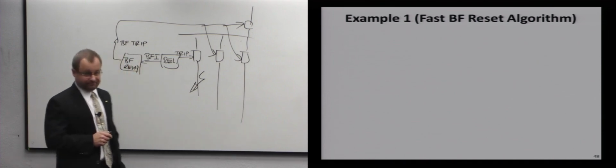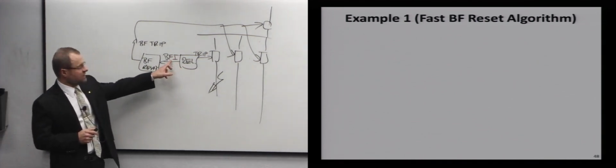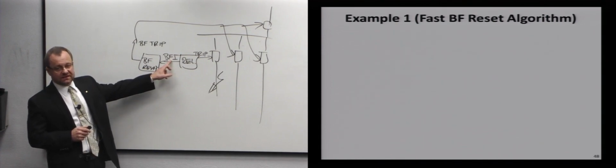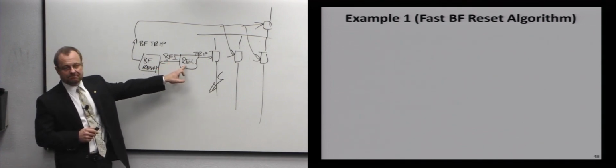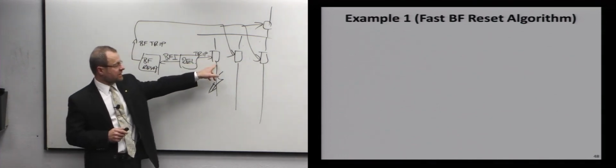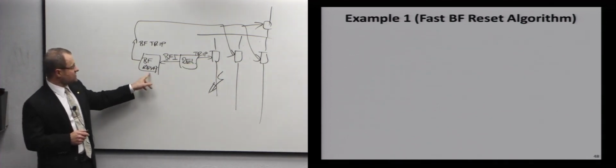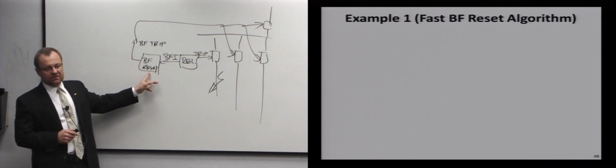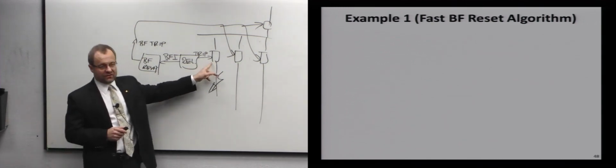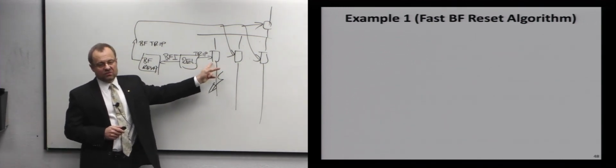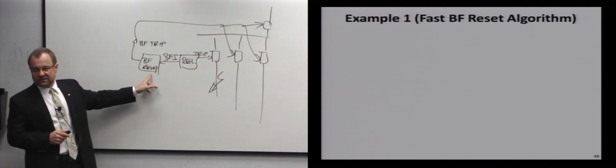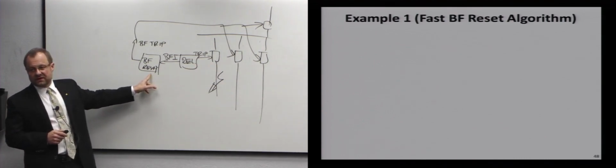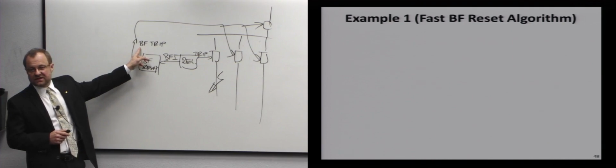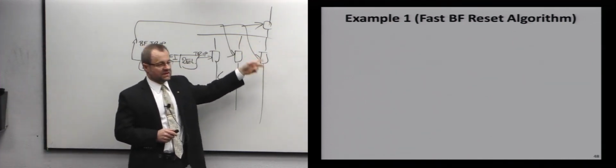The principle is that we receive breaker fail initiate, meaning somebody who trips that breaker tells us, I just tripped that breaker. And then what we do is we take a current from that breaker and we measure if this current disappeared within a certain period of time. So if somebody told me that this breaker will take 3 cycles to open, I may wait for 3.5 cycles, and if I see a current, I will say this breaker failed to open. And I will assert breaker fail trip, and I will dump this entire bus.